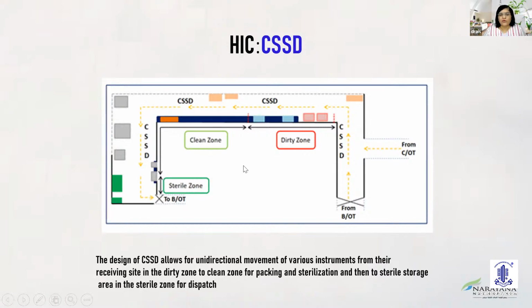This is the design of one of our OTs. You can see that this is the dirty zone, clean zone, and sterile zone. Let's imagine that the OT is over here. The instruments come out from here and go to the dirty zone. They get cleaned, and then after cleaning they move towards drying. Packaging happens over here. Once the packaging is happening, our ETO machine and autoclave sterilizers are all here. The moment the packaging is done and the instruments and packets are dry and have been labeled properly, according to the biological indicators in place, they come out to the sterile zone.